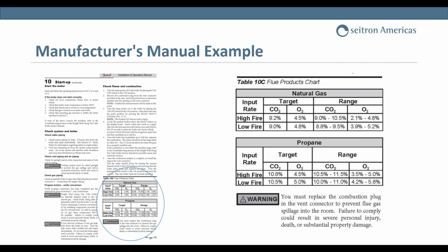We've had some manufacturers now that are pushing the fact that if you do not have an analyzer, or don't set it up properly or commission the boiler properly—especially at startup—they're moving away from actually honoring warranties for certain equipment because it's not set up properly. So it's really, really been moving that way.